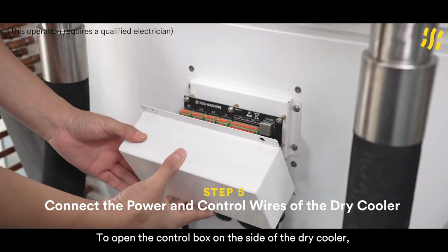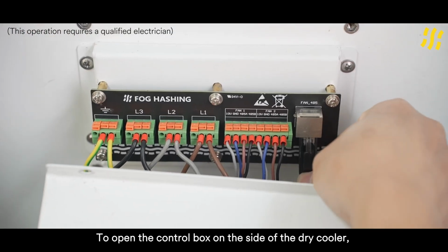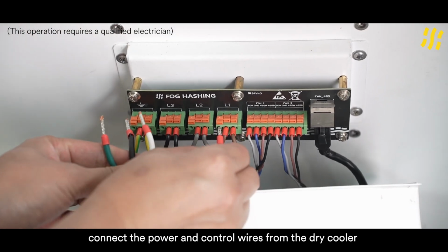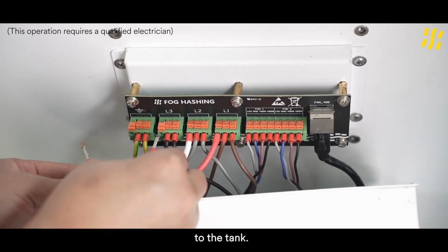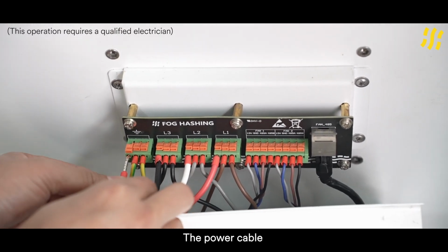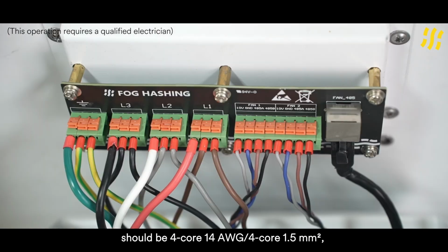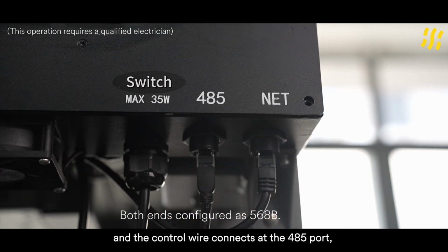Open the control box on the side of the dry cooler, and connect the power and control wires from the dry cooler to the tank. The power cable should be 4 core 14 AWG/4 core 1.5 mm², and the control wire connects at the 485 port using a category 6 shielded Ethernet cable.